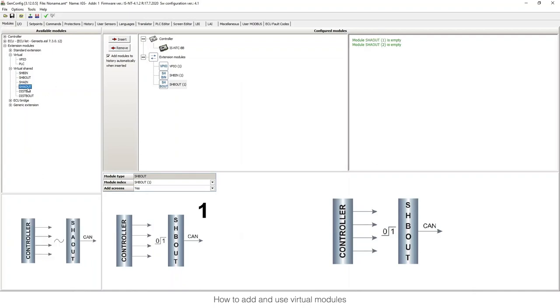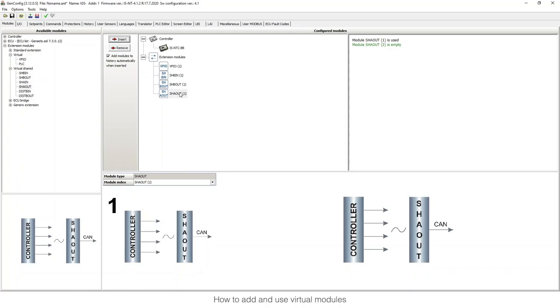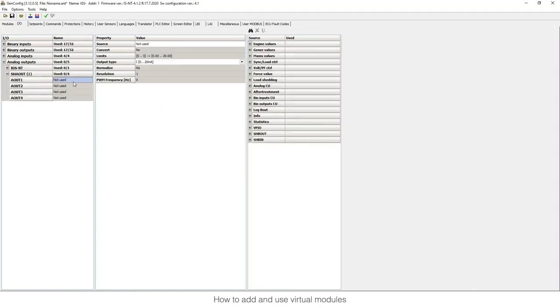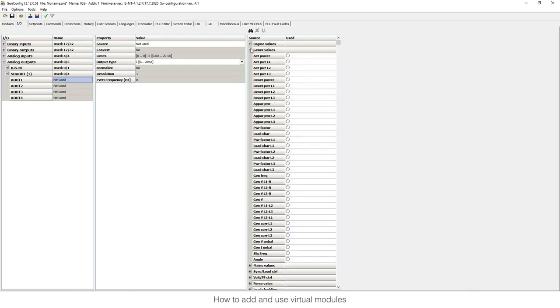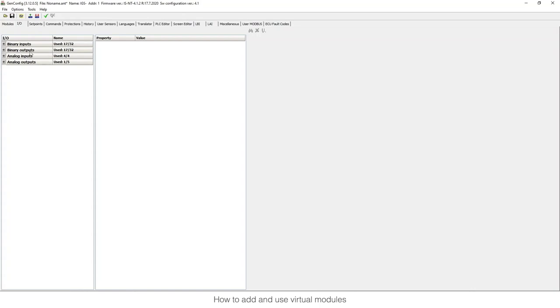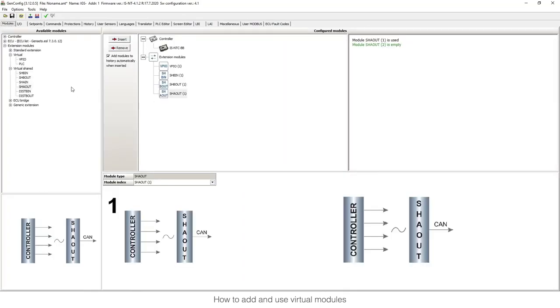For shared analog input and analog output, the logic is exactly the same: analog output in the controller that sends the information, and analog input in the controllers that need to receive it. It is configured in the same way, but now with analog inputs and outputs. For example, I can take the active power and send it from controller one to another controller using shared analog input one.